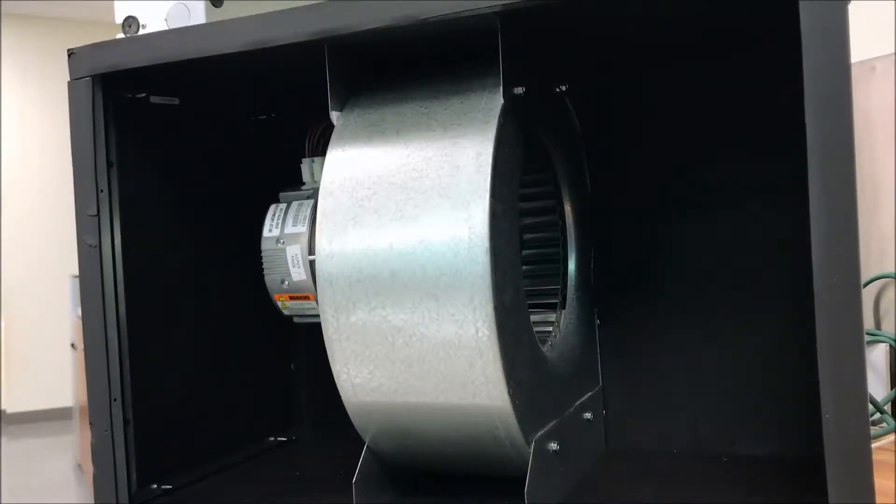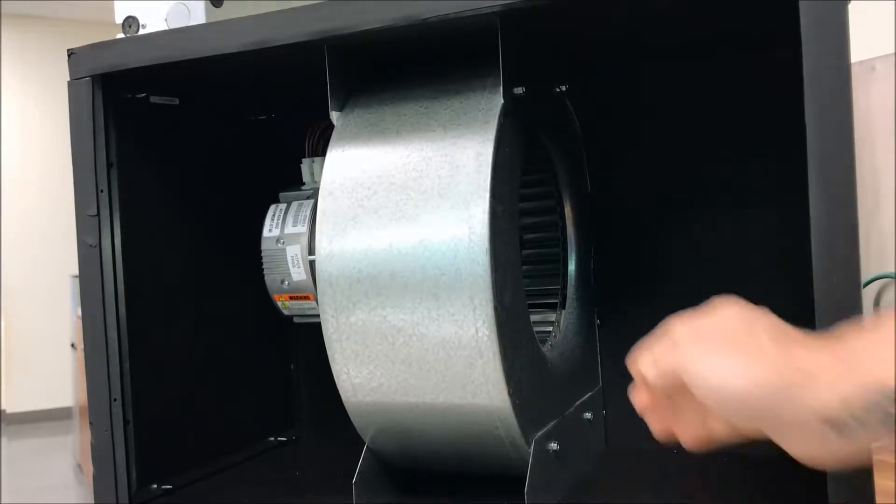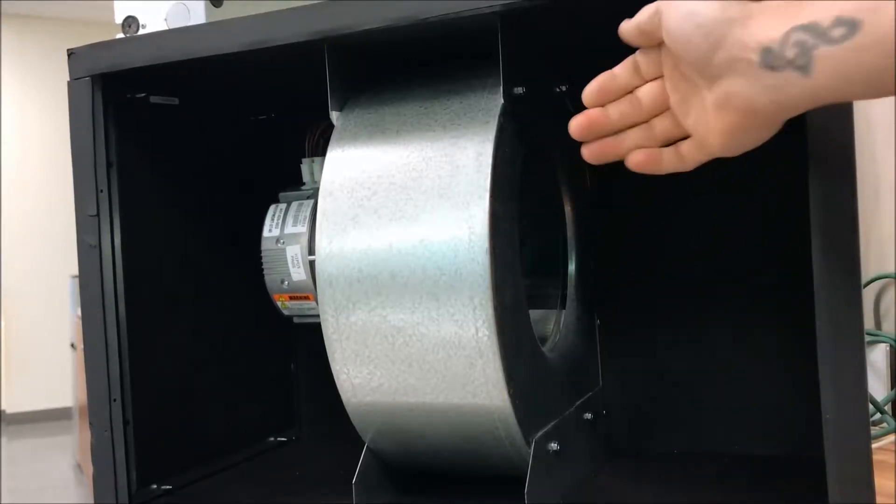The first thing you want to do is to disconnect the power and reach in and spin the blower wheel just to ensure that the motor spins freely.